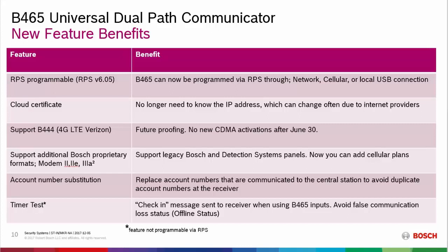And this is the configuration of basically a check-in message. So if you're using the inputs on the 465, you're not getting that check-in message that comes from the host panel. You're just using basically the outputs from that host panel going to the inputs of the 465. You don't get that daily check-in. And then when you're looking at your automation software, you see basically an offline status for all your 465s that are configured this way. Well, now you can configure the 465 to check in itself. So this was an important feature for several of our customers.